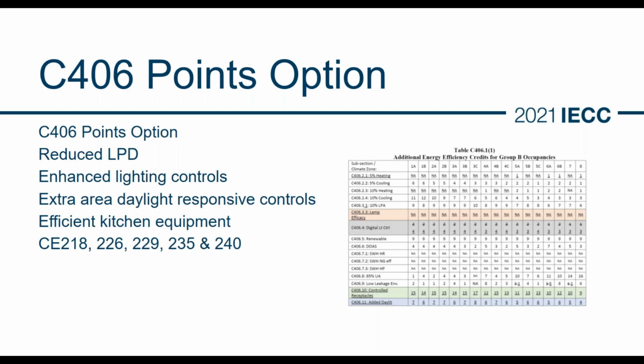And this has been problematic for installers or for code users. So one of the modifications made to this is to say, we're going to go ahead and split the piece of equipment up. And so you can get points by just having an increase in efficiency on your cooling side, either 5 or 10%, or your heating side, either 5 or 10%. And this will provide a lot more flexibility and really make this a much more realistic methodology for doing this. There's also the addition of efficient kitchen equipment, and this was an initiative by the Northwest Energy Efficiency Alliance that was first put into Washington State, but it recognized the fact that commercial kitchen equipment actually uses a significant amount of energy. So now you have the option of installing equipment and getting credit for it from a code compliance standpoint, and you'll get a certain amount of efficiency there.